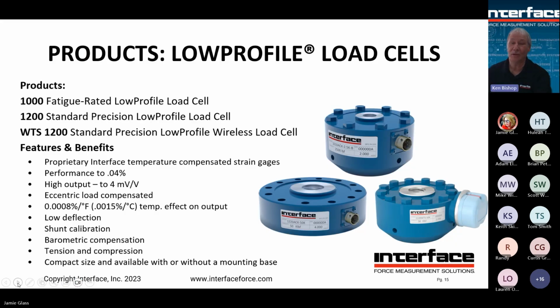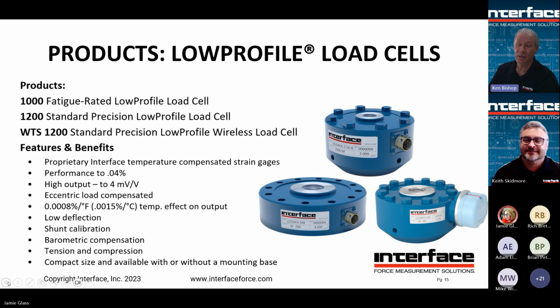There we go. We'll start with the low profile load cells. A lot of you have seen this used in many different applications, but it's perfectly suited for lifting as well, because with the installed base, you basically have a threaded hole in the top and a threaded hole in the bottom, and you can connect rod ends and bearings to it. So that's the load string that you would have when you're doing a lift. An advantage of a low profile load cell is when you have sub 0.1% measurements that need to be made.